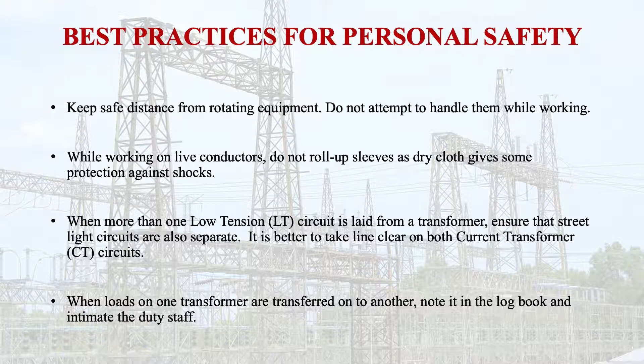When load on one transformer is transferred to another, note it in the logbook and intimate the duty staff. Ensure all 3 blades of AB switches are open before working. There should not be anything energized.